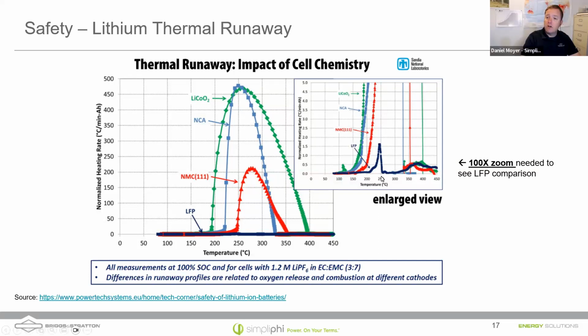So if I see here, it's 250 degrees centigrade, or 200 is where we talked about earlier - it starts at around 200 degrees Celsius. We're forcing it into thermal runaway, and as that cell starts to burn the fuel, the electrolyte is burning, and it starts to heat up, so you see the temperature rising. Basically, when you hit about 240, you're getting the maximum amount of electrolyte vaporizing out of the cell and catching fire outside the cell. That heating rate measures how quickly this happens.